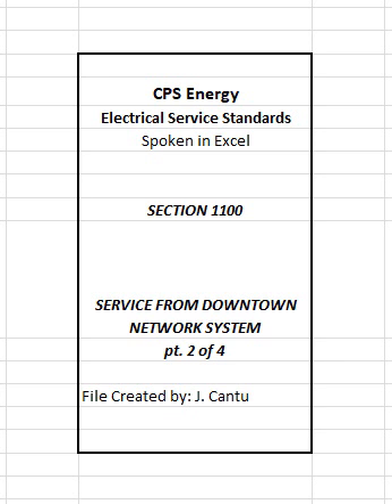Note: where constructing a transformer room within an existing building, CPS Energy will require a structural engineer sealed letter attesting that the construction of such walls and roof are adequate for the conditions and the imposed equipment weight to be supported. 2. The floors of transformer vaults or rooms in contact with the earth shall be of reinforced concrete designed to support CPS Energy transformers with a point load of up to 20,000 pounds each.